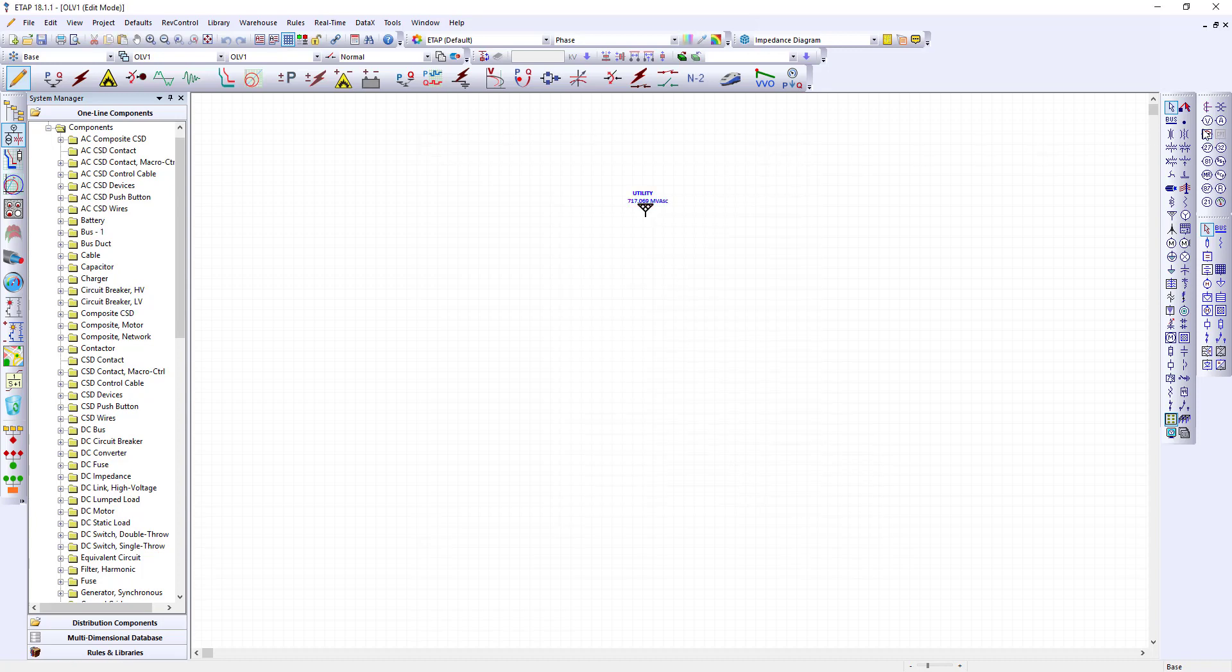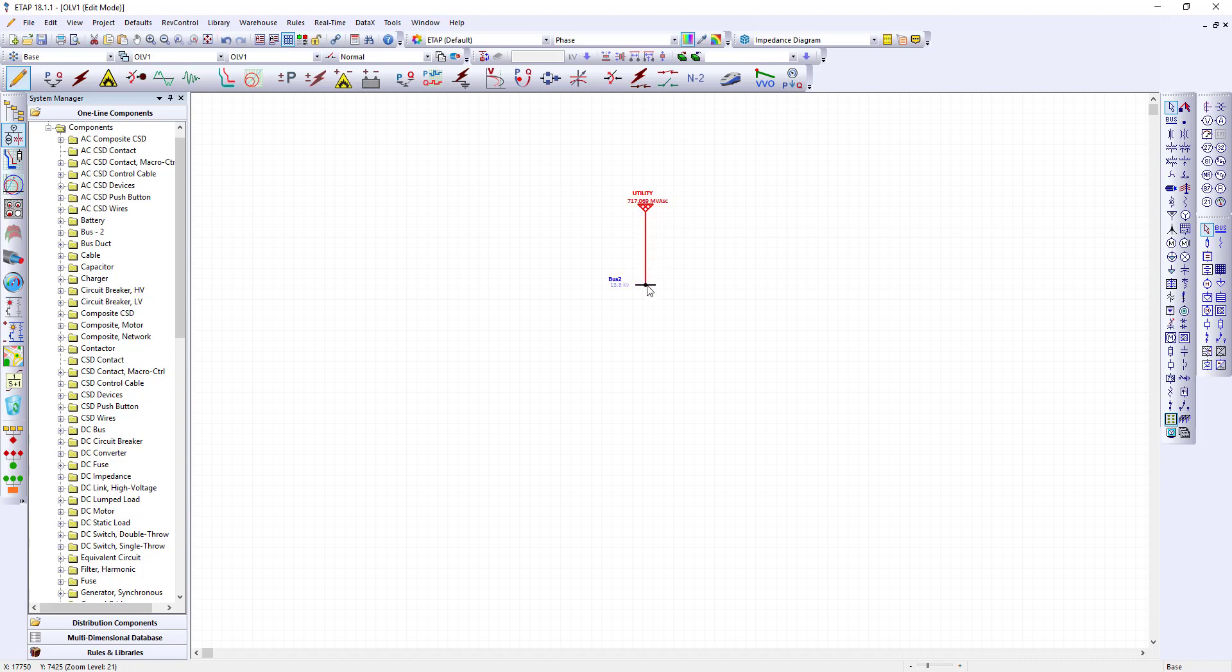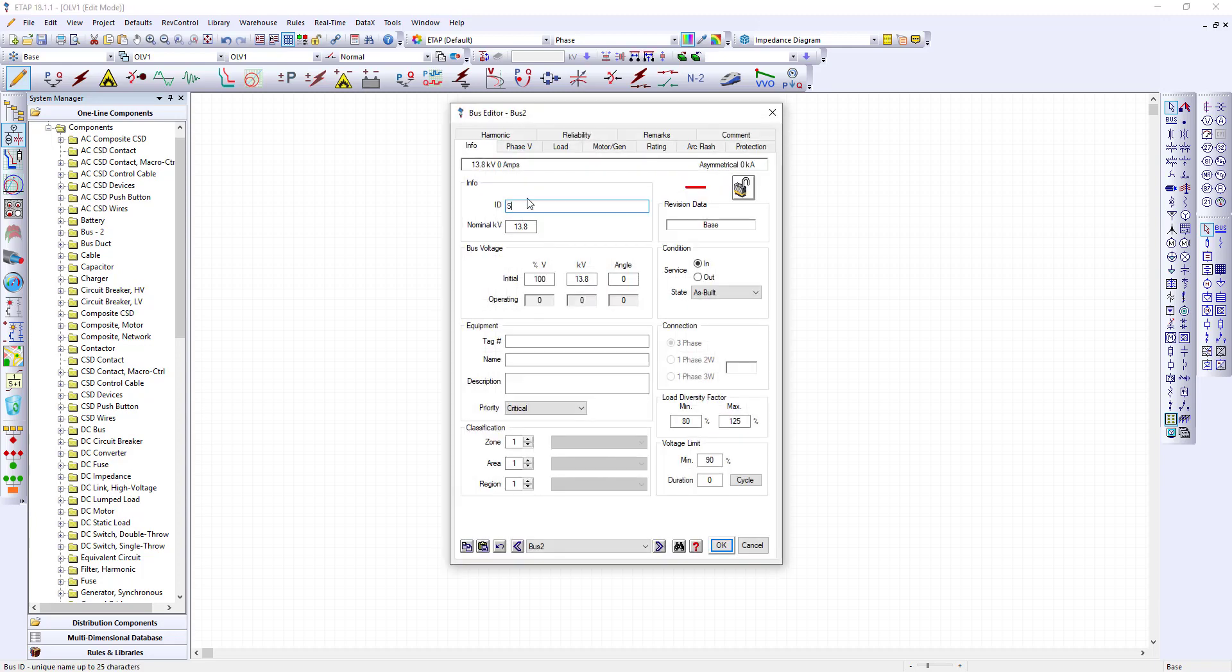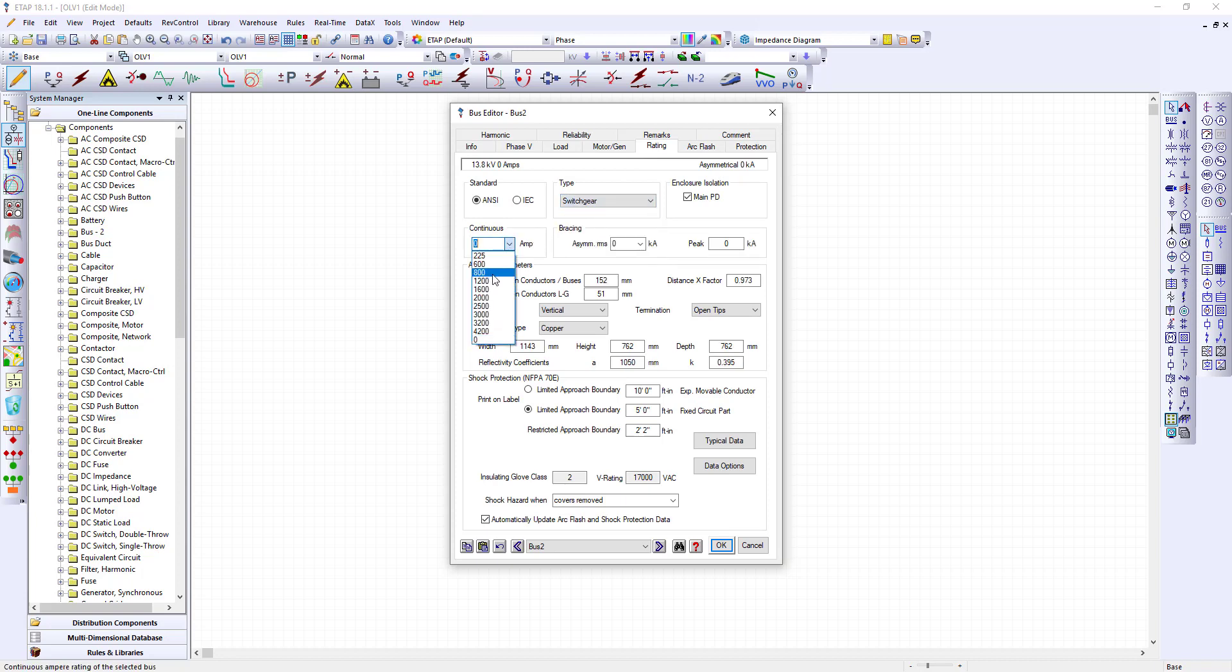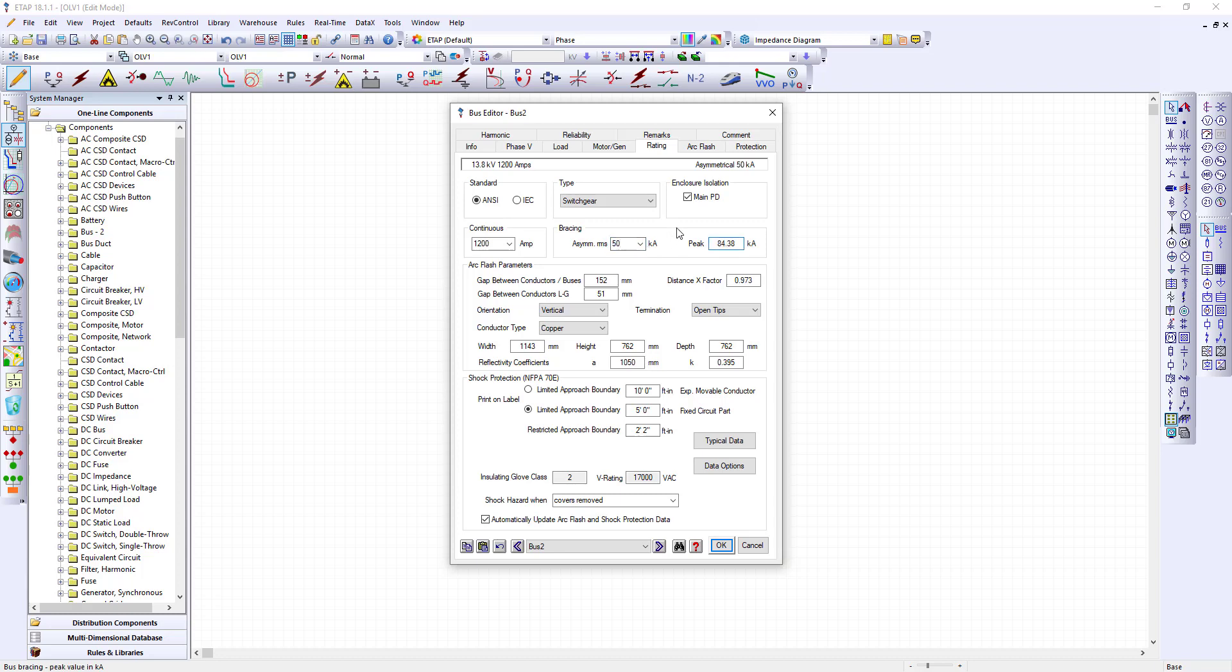Next I will place a bus and I'm gonna click the connection point pin at the bottom of the power grid device and drag it down to my bus. As you noticed this has changed to 13.8 KV. I can also rename it to my switchgear SWGR-001. I can give it the rating and this will be a switchgear at 1200 amps and I'm gonna tell it to make it 50. Click OK.